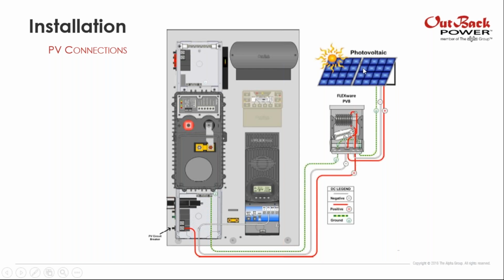If you have a PV array, you just need to install a combiner box. It could be our PV8, for example, or the PV6, or even, if you need a rapid shutdown, our ICS Plus. Everything you need is to bring this positive wiring into the breakers, one breaker for each string, and at the top, all the strings will be joining, and you will have only one positive cable from the combiner box to the PV circuit breaker.